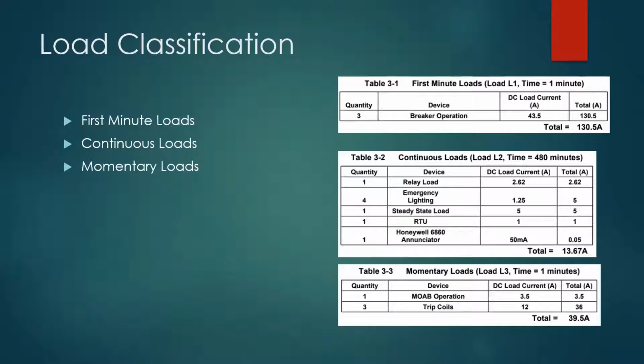For the load classification, it's broken up into 3 different groups. Our first-minute loads, which you can see on the right, is just the operation of the 3 breakers. Our continuous loads involve relaying, metering, the RTU, steady state load, and other things like that. You can see the total amperage added up on the right. And our momentary loads, which could happen at any point in our battery's duty cycle, for this case would include MOAB operation and the trip coils.